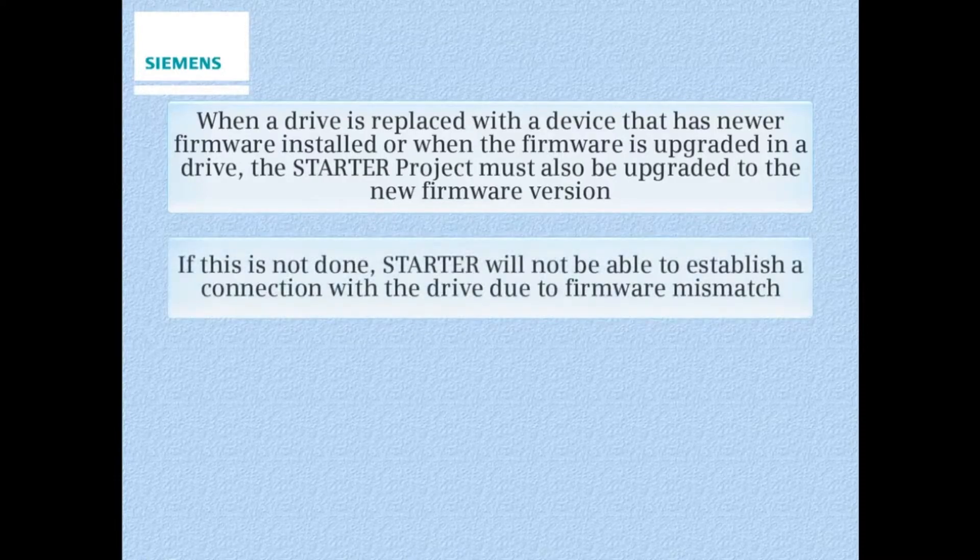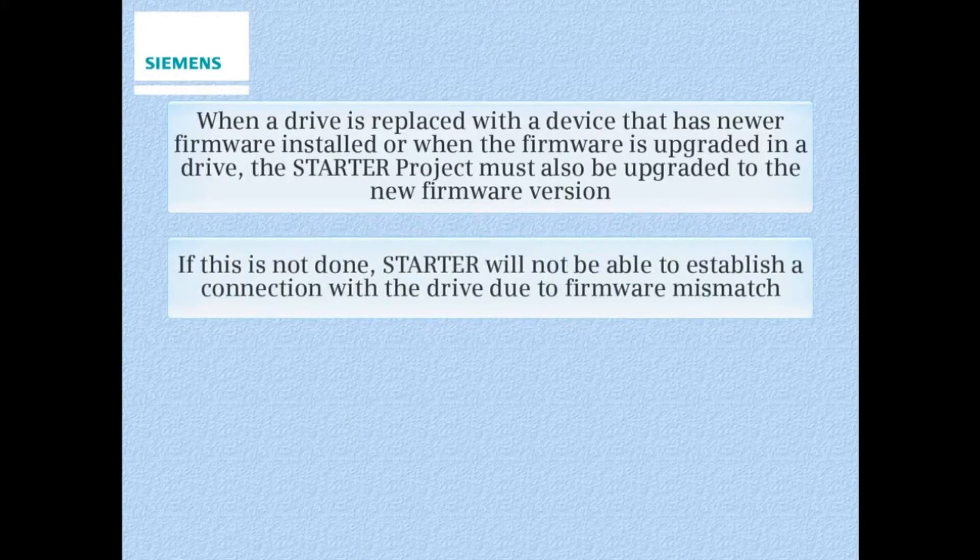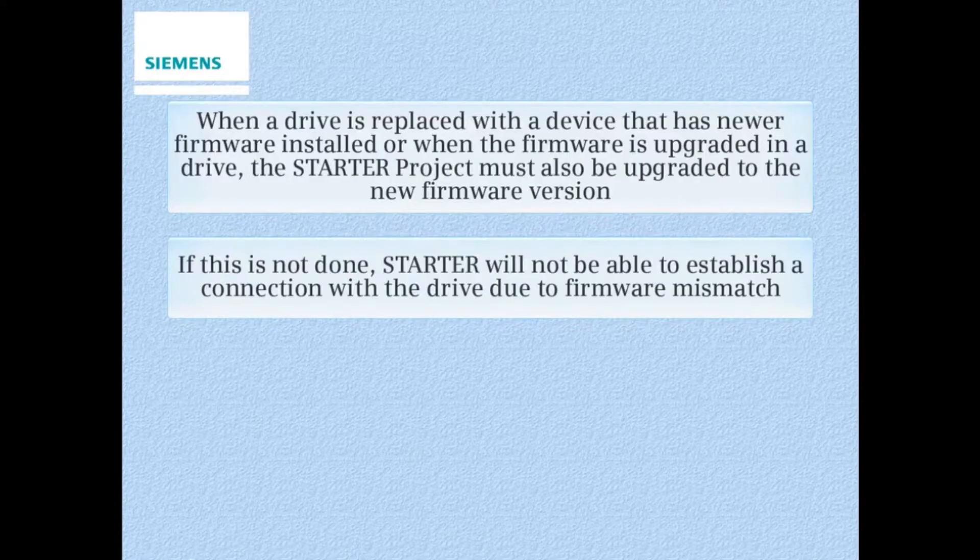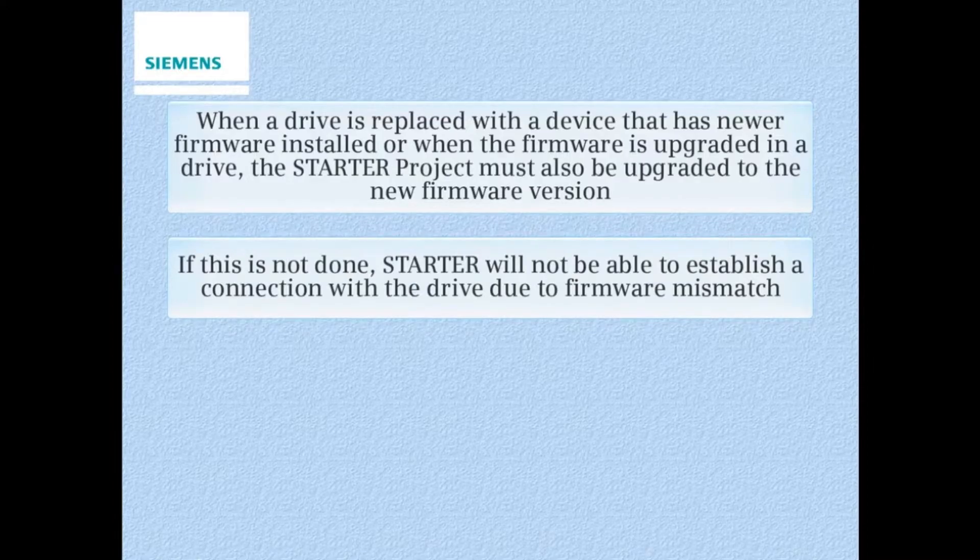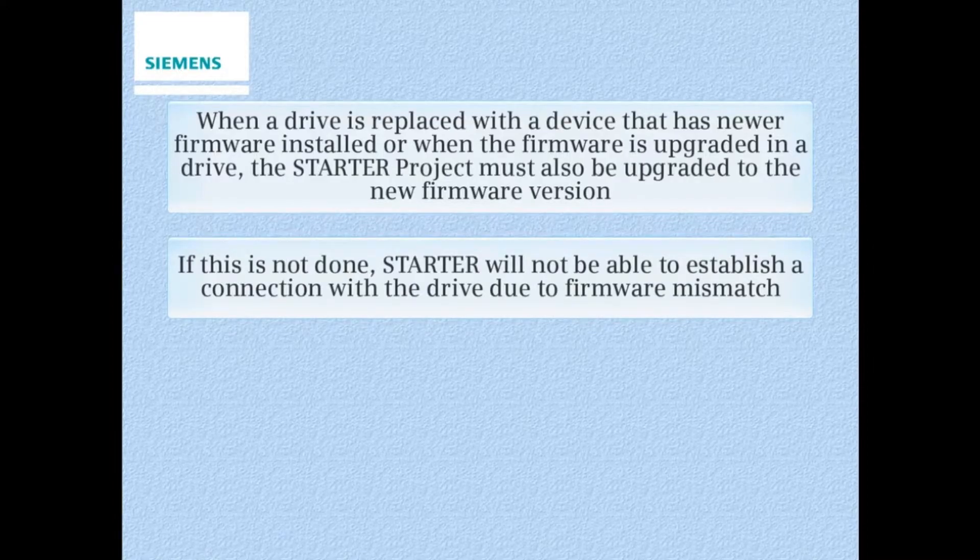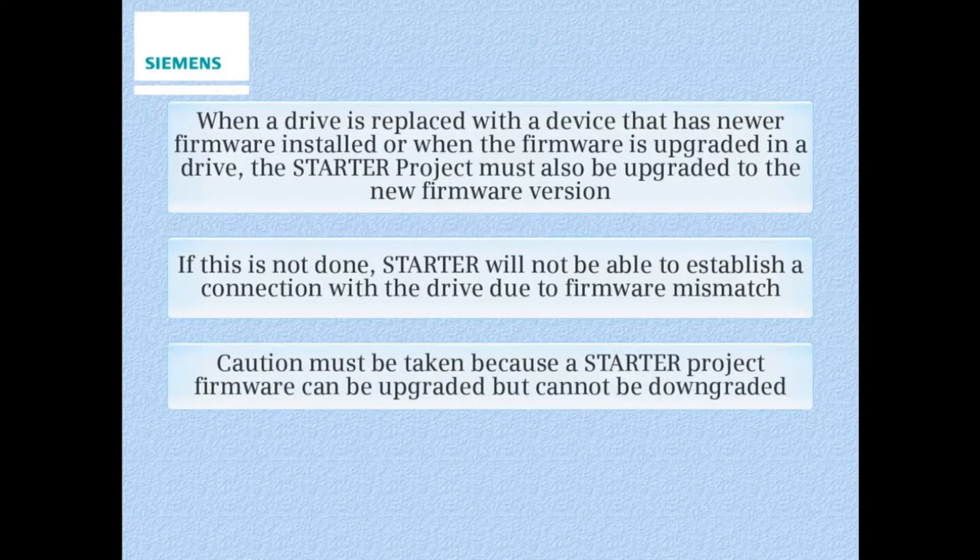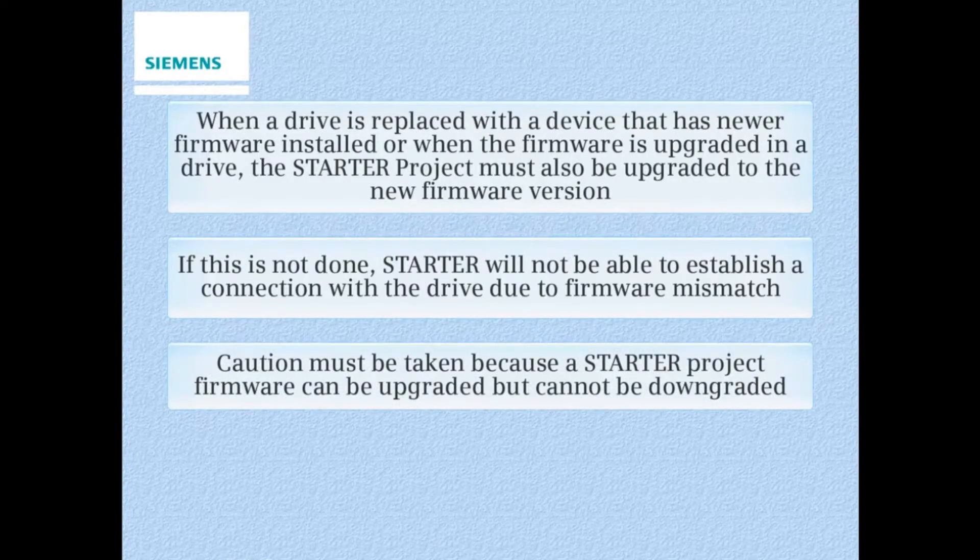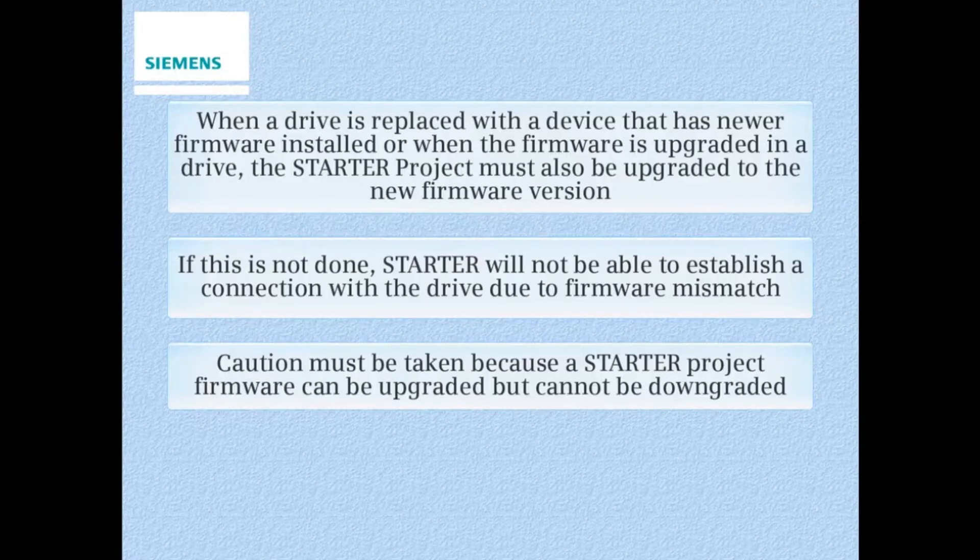If this is not done, Starter will not be able to establish a connection with the drive due to firmware mismatch. Caution must be taken because Starter Projects firmware can be upgraded but cannot be downgraded.